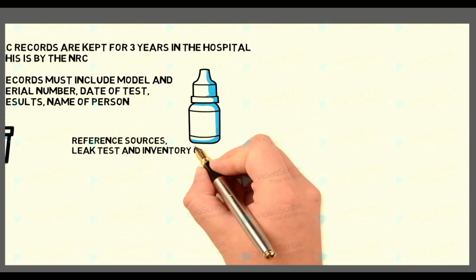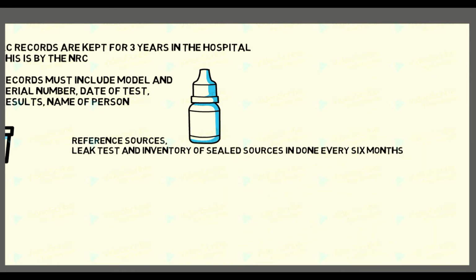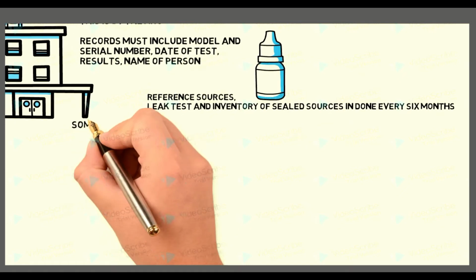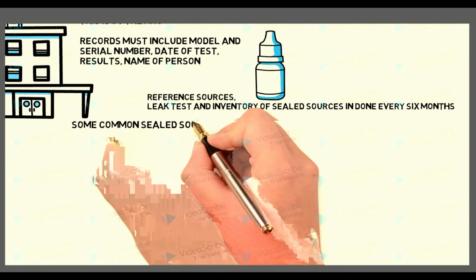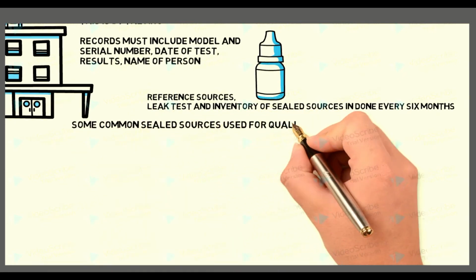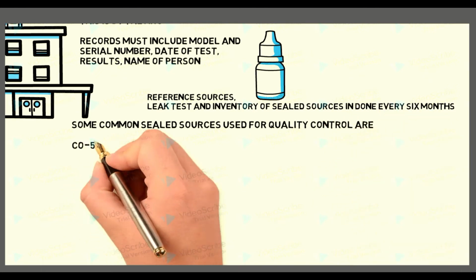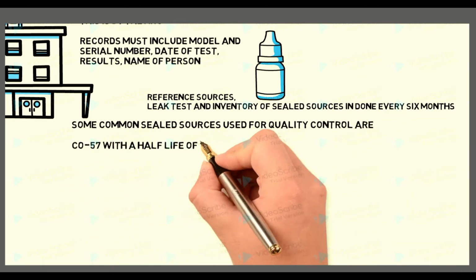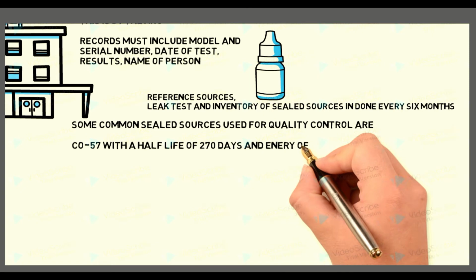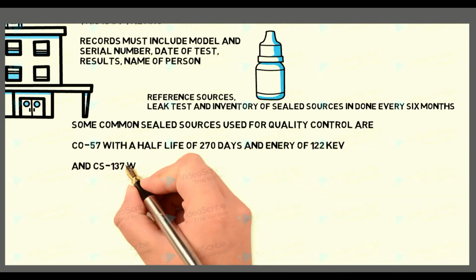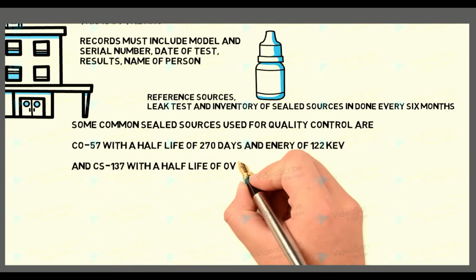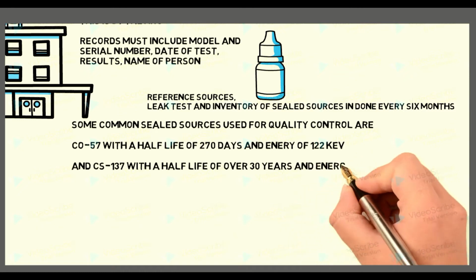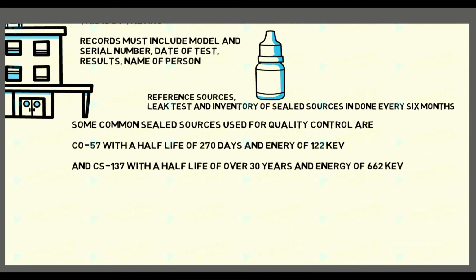Reference sources. A leak test and inventory of sealed sources is done every 6 months. Some common sealed sources that we use in nuclear medicine for quality control are cobalt-57 with a half-life of 270 days and the energy of 122 keV, and cesium-137 with a half-life of 30 years and energy of 662 keV.